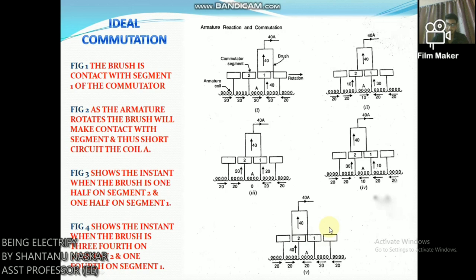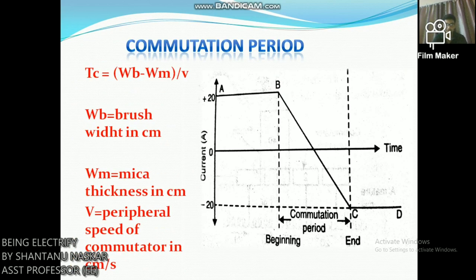Figure 5 shows the instant when the brush is in contact only with segment 2. The brush again conducts 40 amperes: 20 amperes from coil A and 20 amperes from the adjacent coil. The current in coil A is now 20 amperes but in the reverse direction. Thus coil A has undergone commutation. Each coil undergoes commutation in this way as it passes the brush axis. Note that during commutation, the coil under consideration remains short-circuited by the brush.